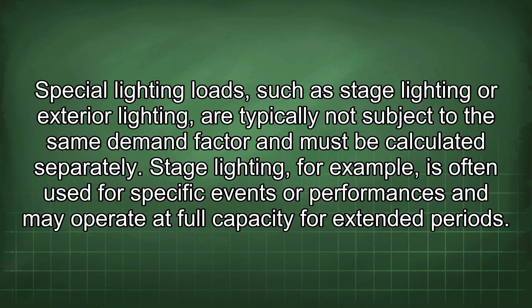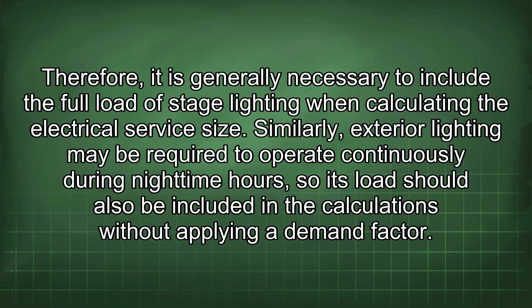It is important to note that the demand factor applies only to the general lighting load. Special lighting loads, such as stage lighting or exterior lighting, are typically not subject to the same demand factor and must be calculated separately. Stage lighting, for example, is often used for specific events or performances and may operate at full capacity for extended periods. Therefore, it is generally necessary to include the full load of stage lighting when calculating the electrical service size. Similarly, exterior lighting may be required to operate continuously during nighttime hours, so its load should also be included in the calculations without applying a demand factor. In addition to the NEC requirements, local building codes may have additional requirements or restrictions regarding the application of demand factors.